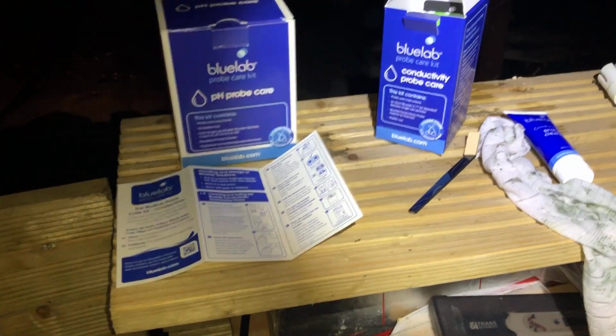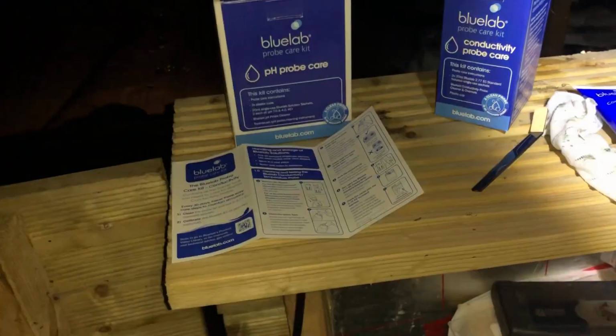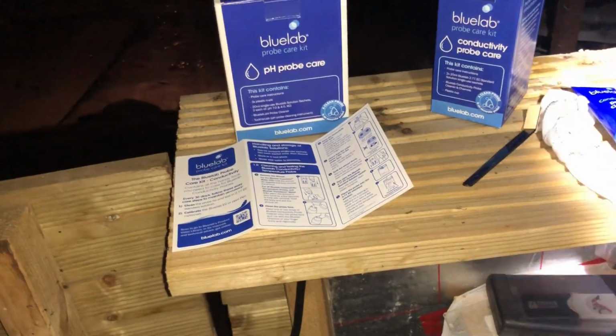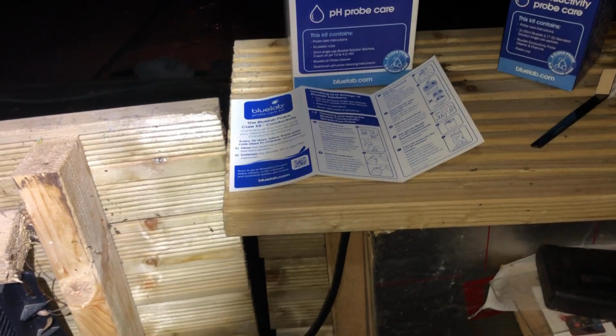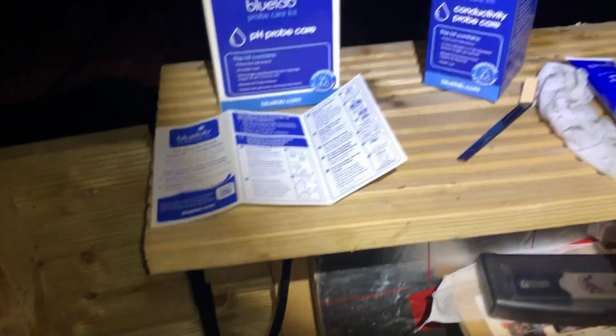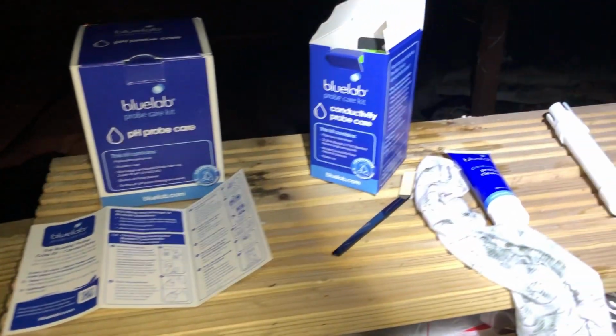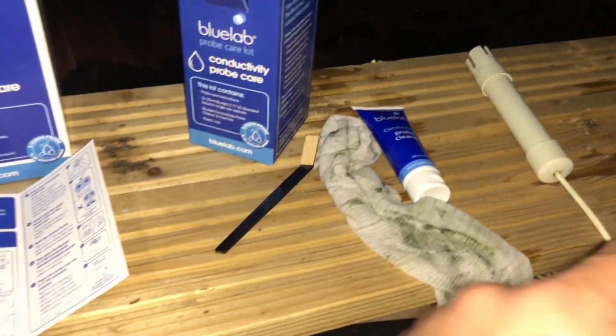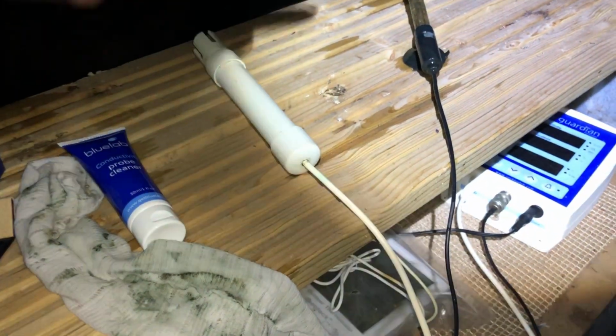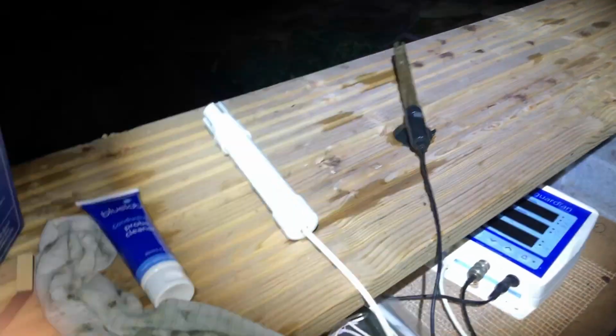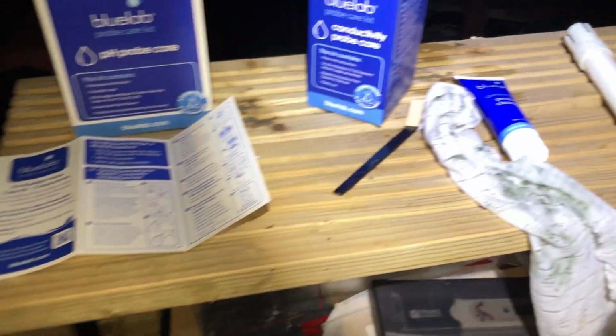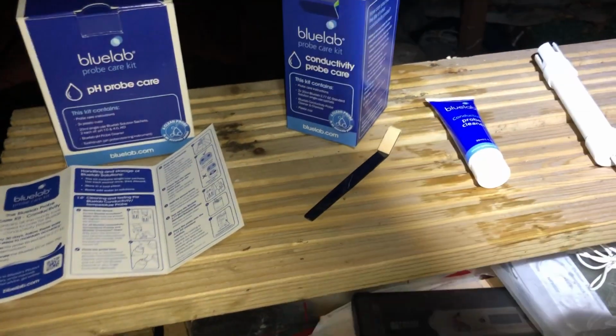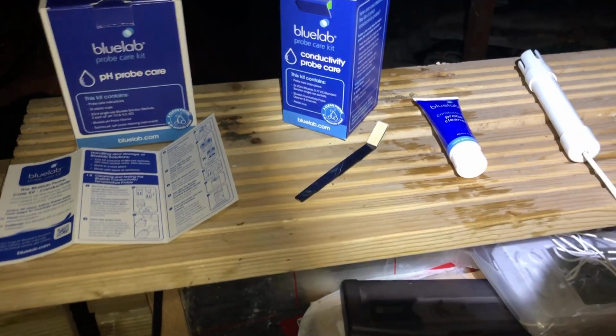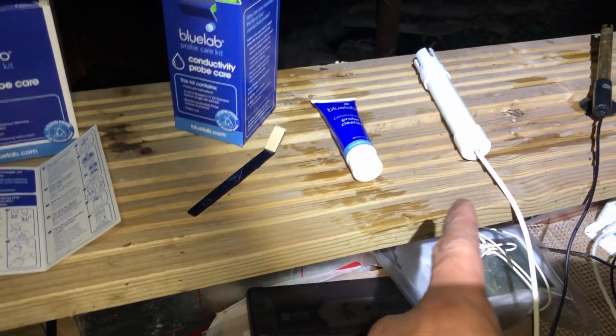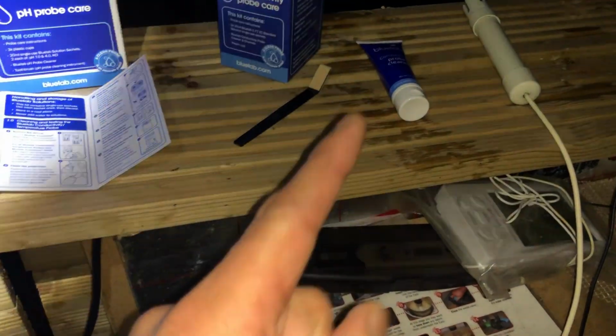So that is worthwhile, what they say, once a month. So it can change. So it's worth a crack. I think the pH probe, you have to put it in one of these liquids for 24 hours. So I will do that and leave that overnight and then come back again tomorrow to do that. So I'll just get that out of the way. So I'll just clean the conductivity one and hopefully get that one calibrated.